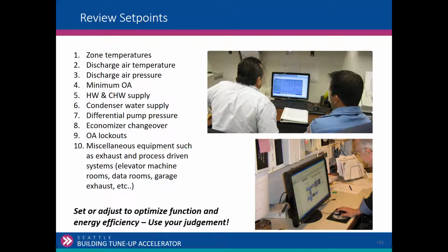Discharge air temperature and pressure. If you've got multi-zone systems, central station air handlers with multi-zone systems, these are two critical things that will affect fan energy and cooling energy. Minimum outside air, ventilation. My rule of thumb, I had mentioned this earlier, is 30%. If it's more than 30% outside air, then I mark that down as a red flag. I'll follow up and ask, do you need to provide all this makeup air for a kitchen hood down in this area, or some other process exhaust? But 30% outside air is a high number for minimum, on a day like today. It can be higher than 30% for cooling, but we're using it for cooling, not ventilation. So that's my red flag level when I look at minimum outside air settings.